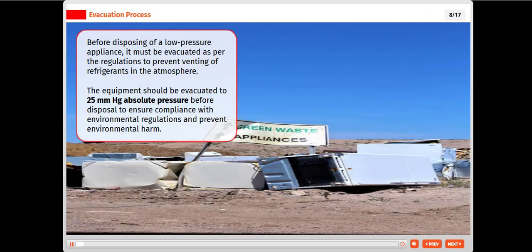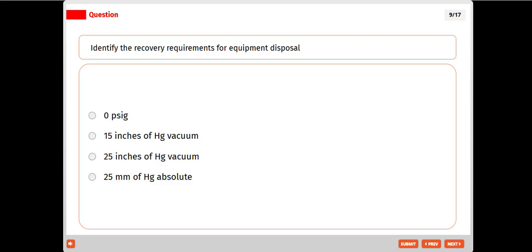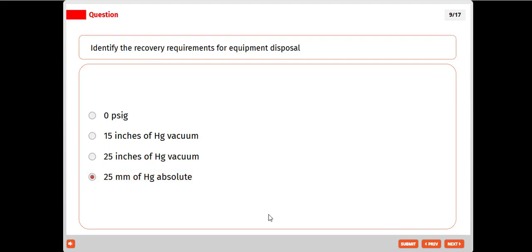Before disposing of a low-pressure appliance, it must be evacuated as per the regulations to prevent venting of refrigerants in the atmosphere. The equipment should be evacuated to 25 millimeters of mercury absolute pressure before disposal to ensure compliance with environmental regulations and prevent environmental harm. Identify the recovery requirements for equipment disposal: 25 millimeters of mercury absolute.